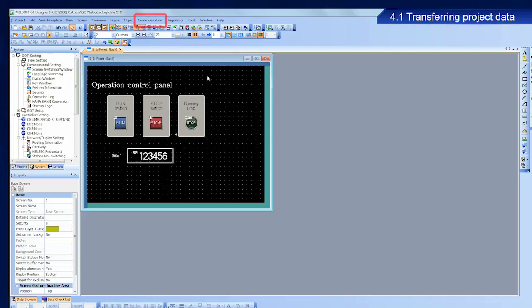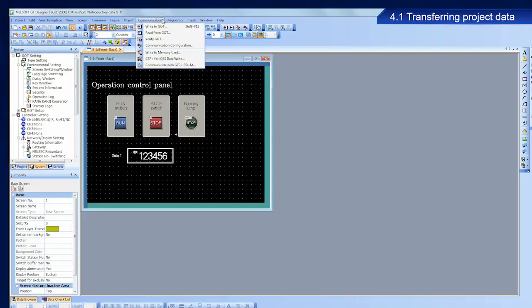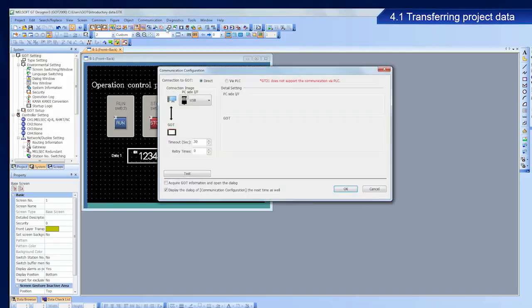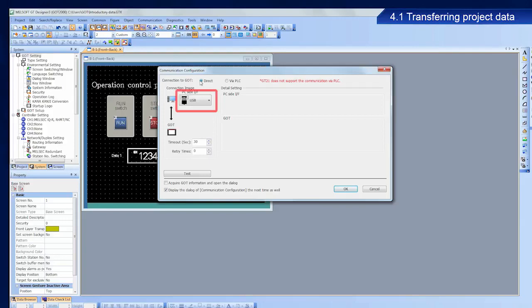From the menu bar in GT Designer 3, select communication and then write to GOT. Confirm the settings. Direct should be selected for connection to GOT and USB should be selected for PC side IF.